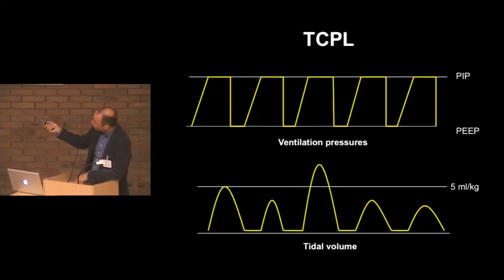Let's assume this is a pressure trace and a volume trace during time cycle pressure limited ventilation. We set the PEEP, we set the peak pressure, and the machine delivers these pressures every breath. You can see that the tidal volume is variable, sometimes below the target you wanted to reach, let's say 5 mLs per kilo, sometimes too high. In the end, if you look at these 5 breaths, only one of the breaths actually reached the tidal volume that you as a clinician are targeting. This is typical for time cycle pressure limited ventilation because there are differences in compliance and resistance, and as the baby breathes in, it assists the mechanical breath, and this will change the tidal volume.